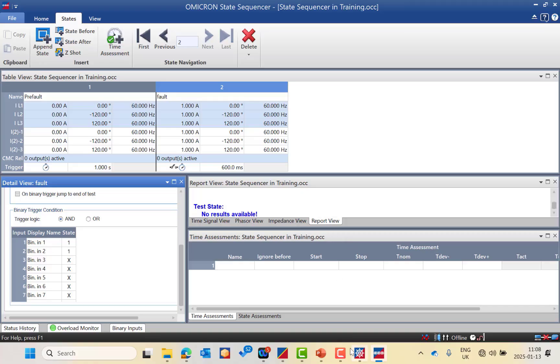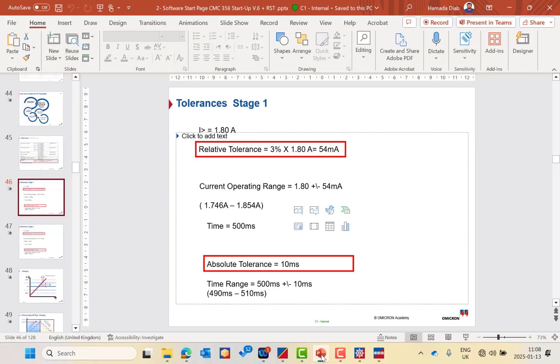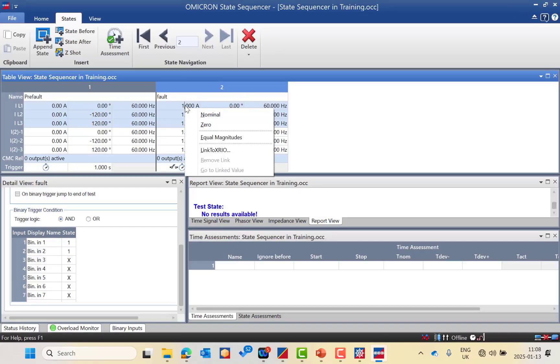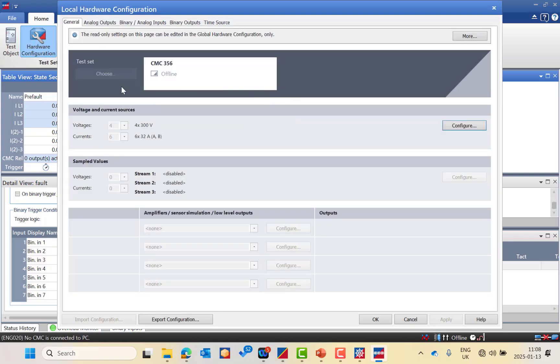As mentioned in the presentation, this is a general test module, which means I have to add manual assessment based on the relay tolerance and the relay user manual. For example, we have an overcurrent stage at 1.8 A with a tolerance of ±54 mA, meaning the operating range is from 1.746 A up to 1.854 A. I will demonstrate this as a 3-phase example.